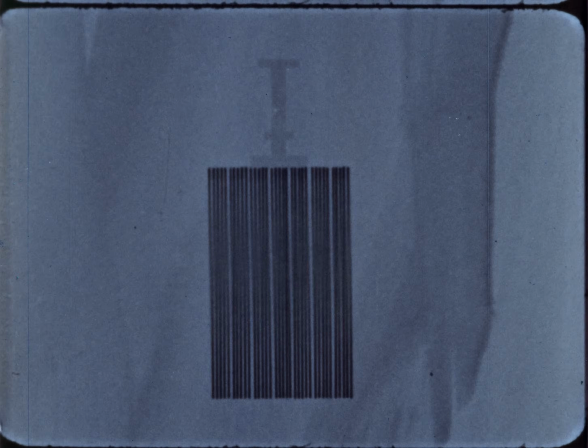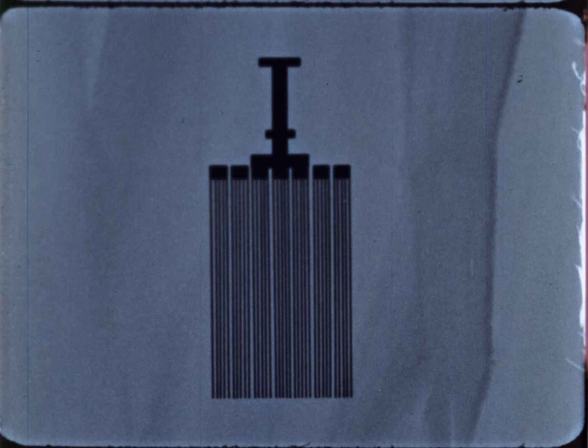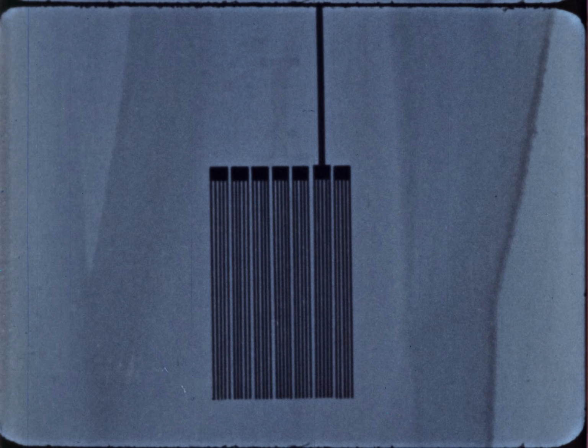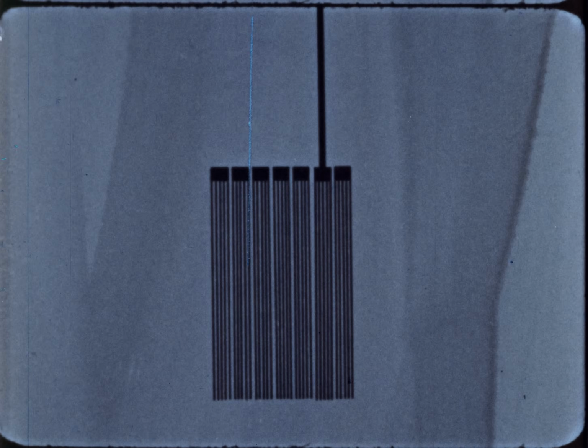741 nuclear fuel tubes make up the reactor core. These tubes are grouped into 7 fuel bundles, 6 peripheral and a center bundle. With the proper tools, we can fuel and refuel the core as a whole. Or, if necessary, we can replace individual bundles without removing the entire core.